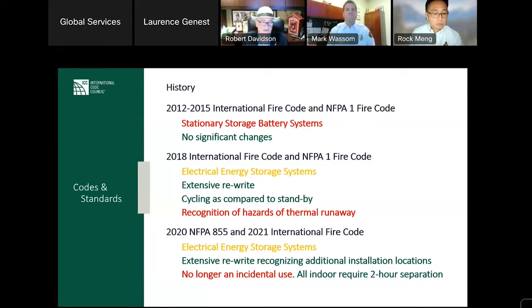So we extensively rewrote both the 2018 Fire Code IFC and the NFPA 1 Fire Code. Now they were known as electrical energy storage systems, recognizing that these are going to be cycled. They're not sitting in standby waiting. And that cycling, temperature changes, the hazard risk changes, and what can happen with a thermal runaway of a large system was recognized.